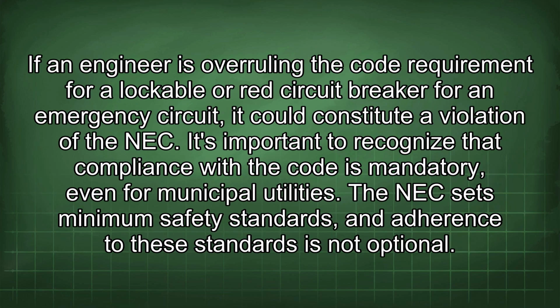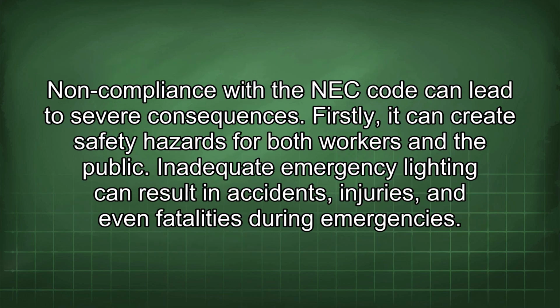If an engineer is overruling the code requirement for a lockable or red circuit breaker for an emergency circuit, it could constitute a violation of the NEC. It's important to recognize that compliance with the code is mandatory, even for municipal utilities. The NEC sets minimum safety standards, and adherence to these standards is not optional. Non-compliance with the NEC can lead to severe consequences.